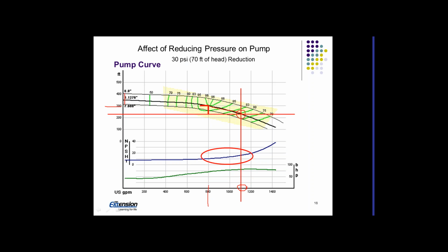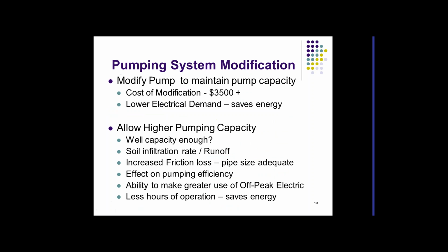One is that it's going to require more head height, water column height above the intake of the pump. So my net positive suction head requirement is going to be higher. It's also going to take more power, I should say, not necessarily more energy, more power to operate that pump. So that can be a factor. But it will save energy in the end, and we'll explain that in a little bit.